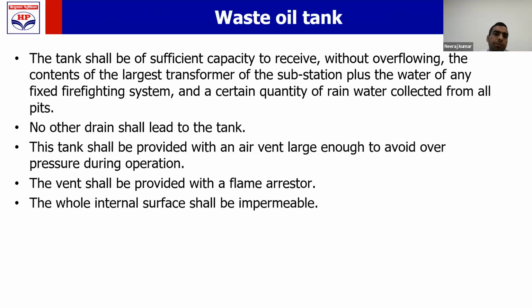वेस्ट ऑयल टैंक का डिजाइन कैसा होगा, कैसा बनाना है? The capacity of the waste oil tank shall depend upon 3 things. How much oil is there in your transformer? How much water may come during rain which may reach this waste oil tank, and a safety margin. So while calculating the capacity of the waste oil tank, you consider the oil from one transformer, or if you are using multiple transformers, then those transformer oil capacities, or the transformer which is biggest among these transformers, the capacity of that transformer, then the water of rain that can come, and keep some safety margin.